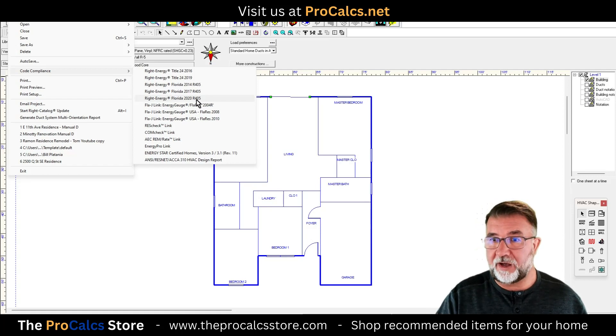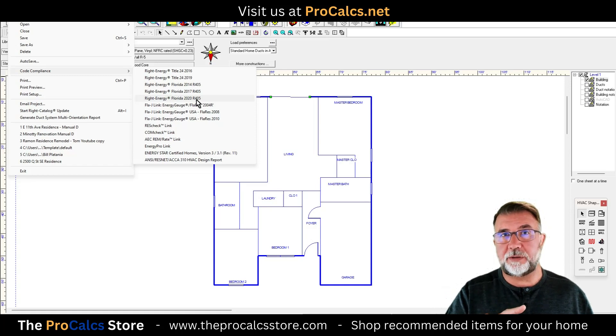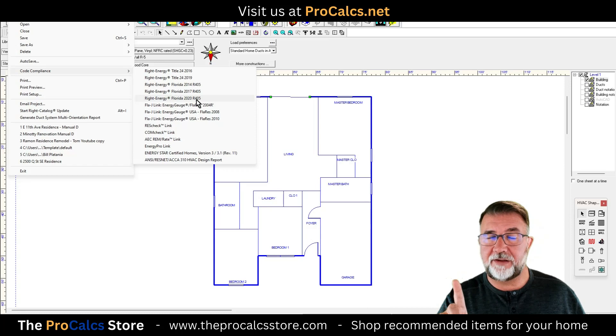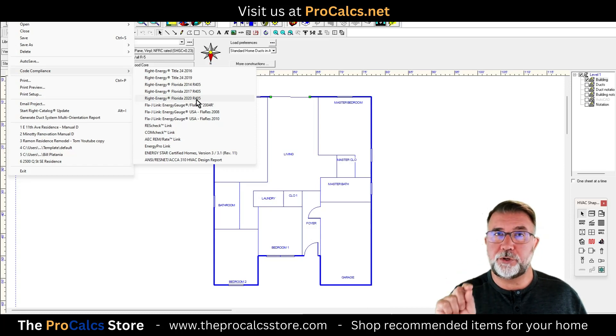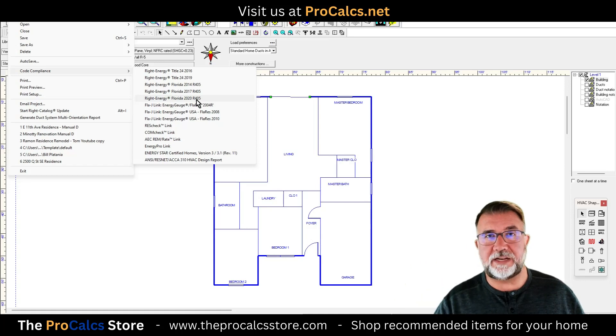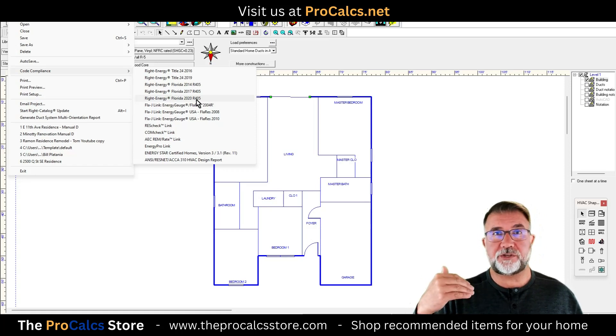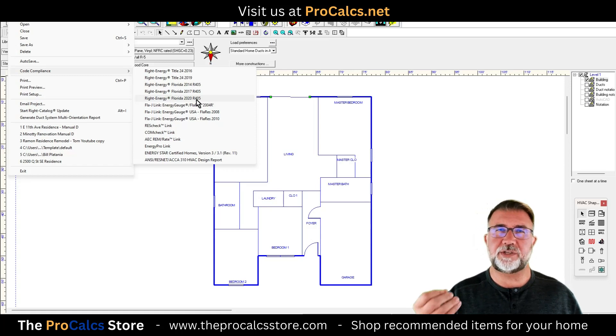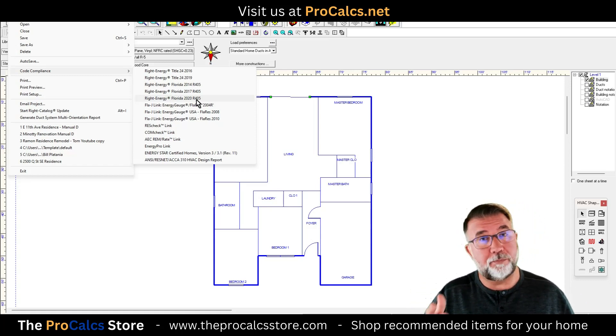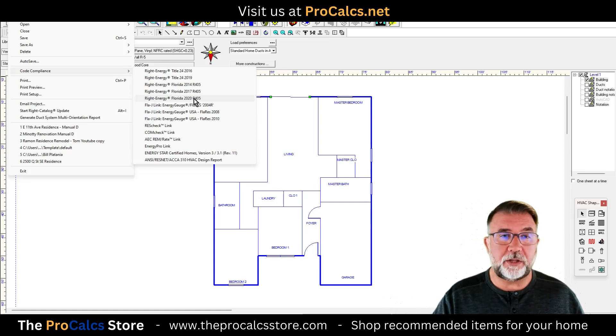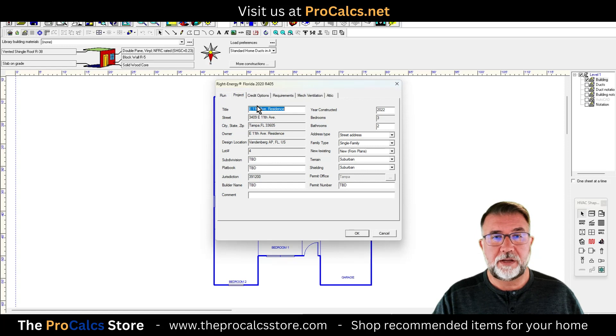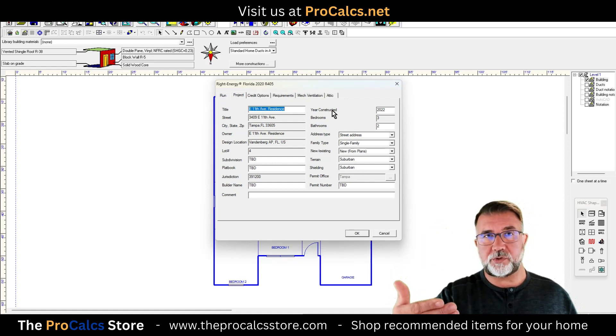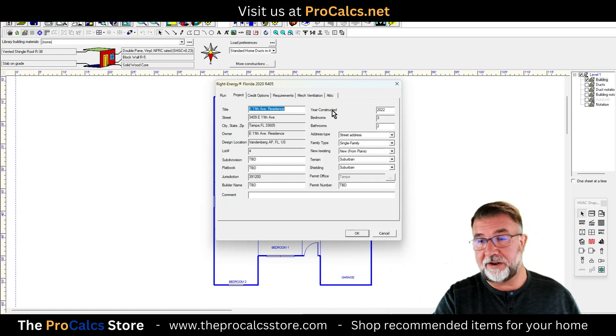This runs R405, which is the performance method. R402 is the prescriptive method, and 99% of houses in Florida won't pass because of its requirements — including air handlers needing to be in conditioned space, ducts in conditioned space, and more restrictive window values, making it more costly to build. When we click on RightEnergy Florida 2020, it opens a file and a lot of the information is automatically extracted from the design.